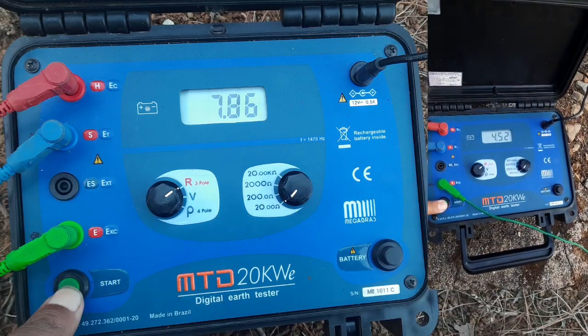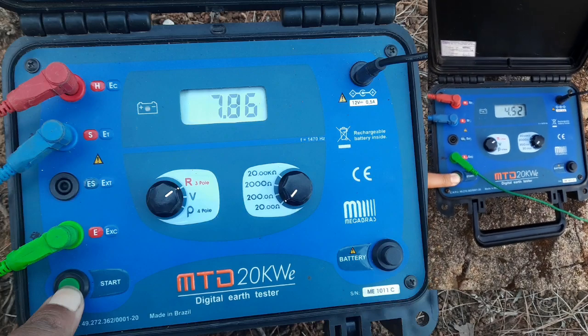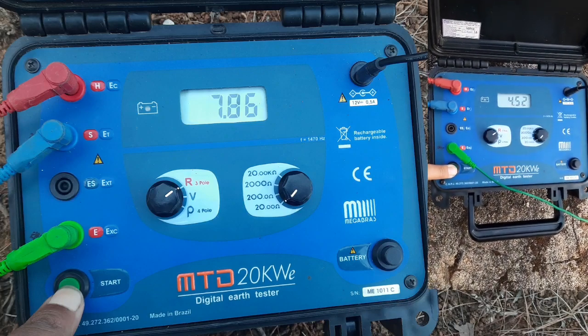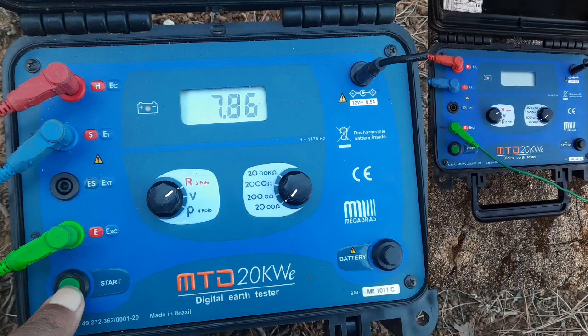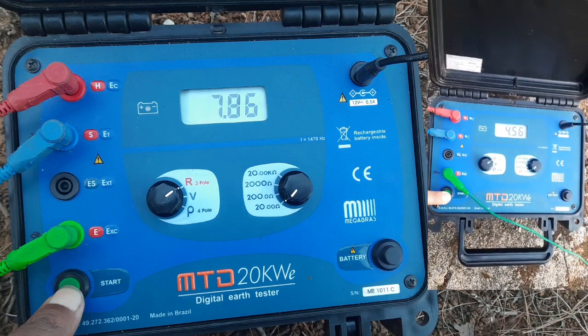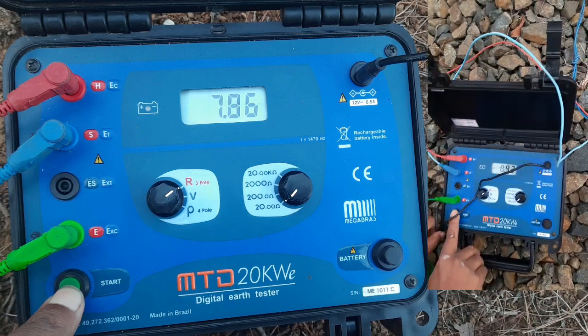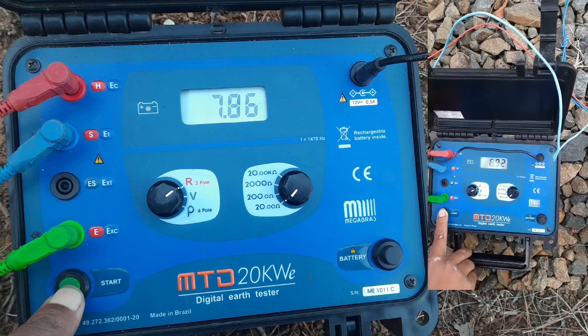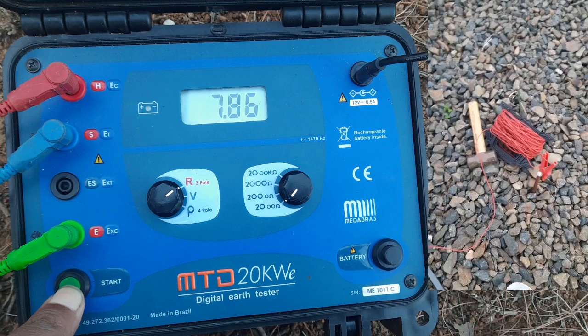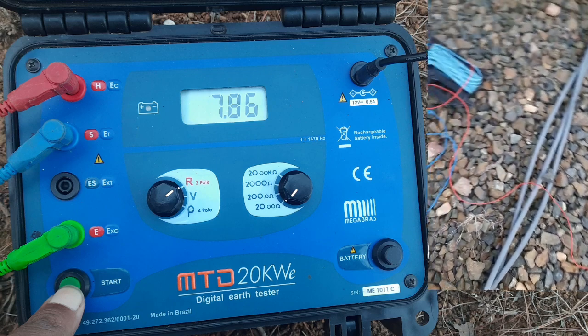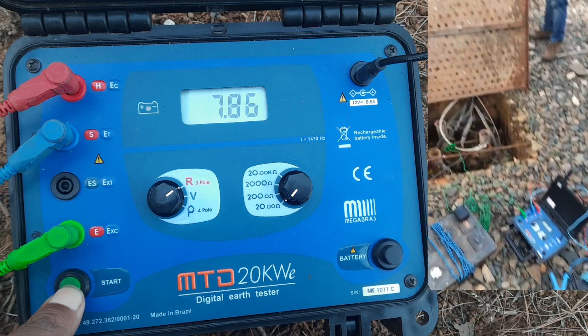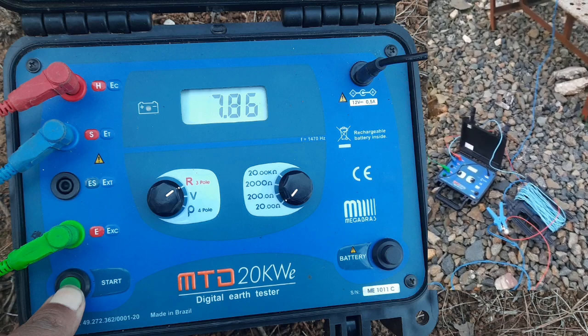Depending on where we keep our selector switch: if we keep it in R, it will measure the resistance. If we keep it in V, we will be measuring the voltage with respect to earth of any equipment. And if you put it in rho, it will give you the measurement of the soil resistivity.